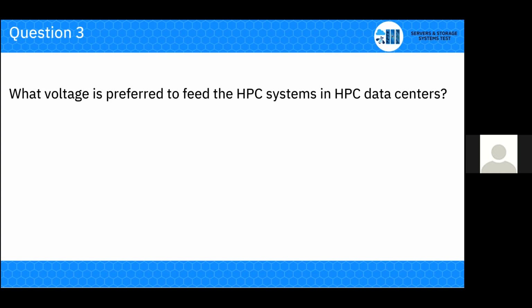I'll speak to the commercial world. Commercial world has gone predominantly to 230, 240 volt single phase. So the distribution into the data center or the IT room is either 480 stepped down in PDUs to 400 volts three-phase inside the IT room. And then it's a question of if you've got UPSs, is the UPS putting out 400 volts or are they putting out 480 volts? And that's where all the commercial people have gone.